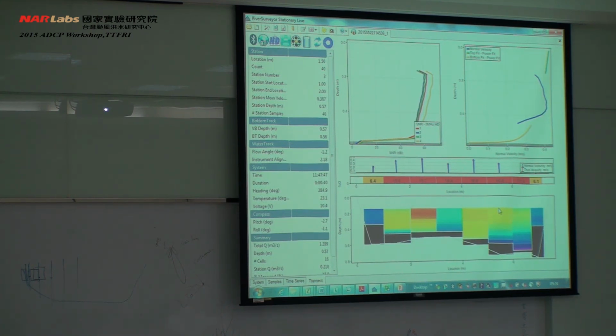So is it necessary? It all comes down to reducing the uncertainty of the measurement. We've ended up with a very good measurement, but the uncertainty is actually quite high. The accuracy of the measurement is good, but the uncertainty is not. This uncertainty is based on the international standards way of calculating uncertainty from measurement of discharge, in their document called the HUG, the Hydrometric Uncertainty Guidance document.